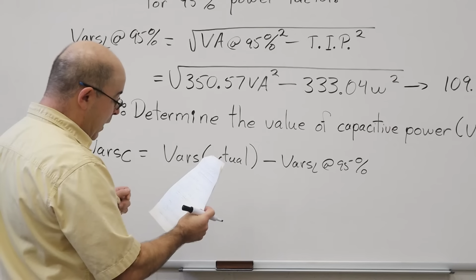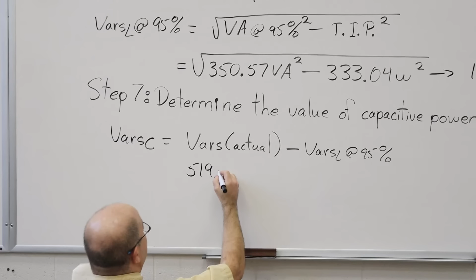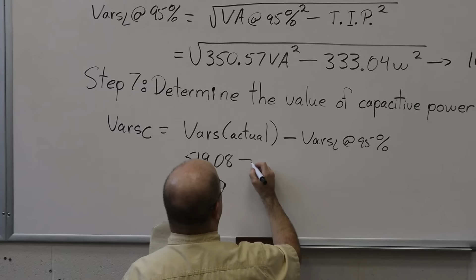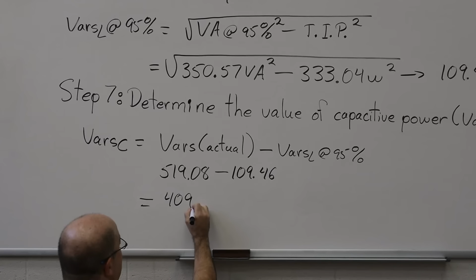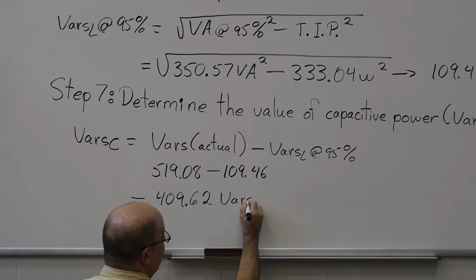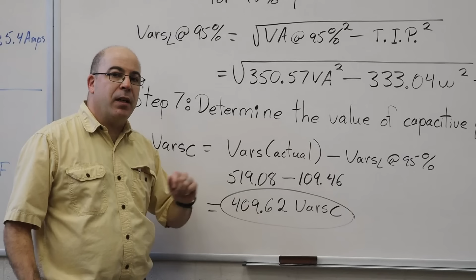Let me check my notes. We're going to take 519.08 VARs and subtract 109.46, and the result should be 409.62 VARs capacitive. This is the amount of reactive power I need to generate using a capacitor.